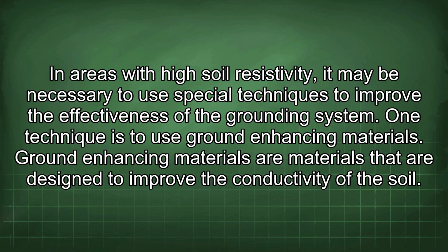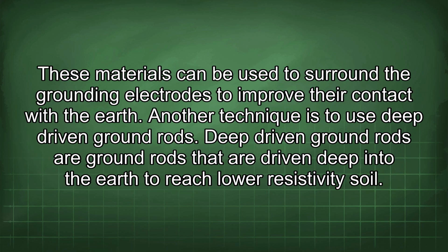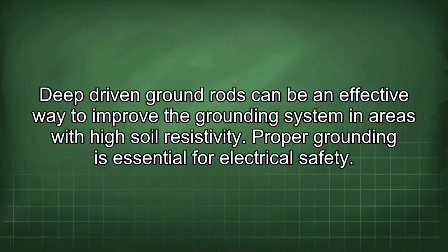In areas with high soil resistivity, it may be necessary to use special techniques to improve the effectiveness of the grounding system. One technique is to use ground-enhancing materials. Ground-enhancing materials are materials that are designed to improve the conductivity of the soil. These materials can be used to surround the grounding electrodes to improve their contact with the earth. Another technique is to use deep-driven ground rods. Deep-driven ground rods are ground rods that are driven deep into the earth to reach lower resistivity soil. Deep-driven ground rods can be an effective way to improve the grounding system in areas with high soil resistivity.